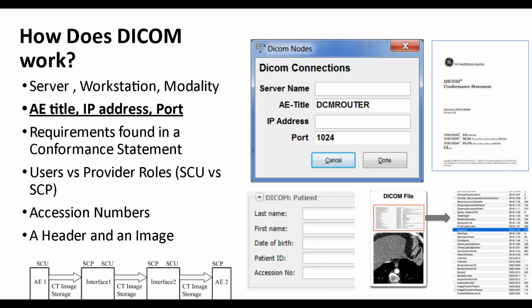So moving along here, let's talk about the basics of how to set up DICOM. I want to cover this prior to going through the whole lab portion, and yes, we are going to do a significant lab portion on this. There are three things you need to write down. All machines in DICOM are going to have what's called an application entity title, or AE. We just call it an AE title. They're going to have, of course, an internet protocol address, or IP address, and we do use TCP/IP. And because we're using TCP/IP, another thing we're going to have is a port.